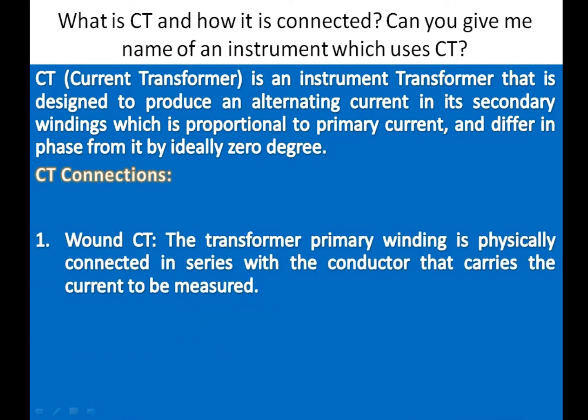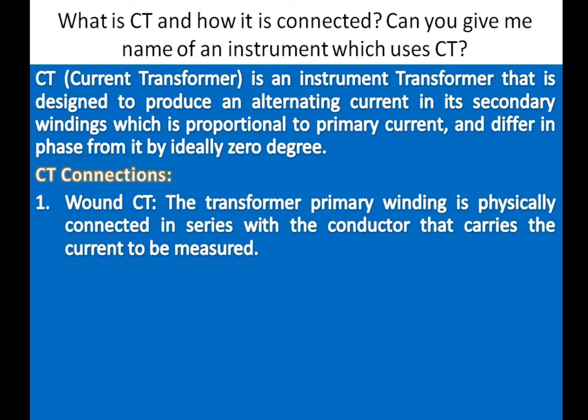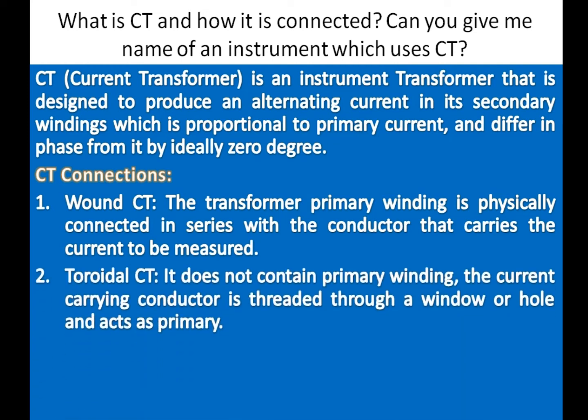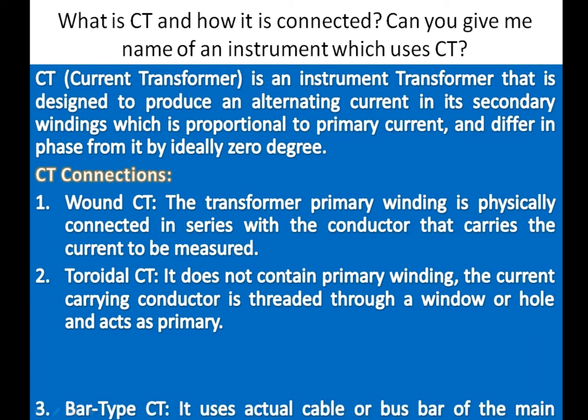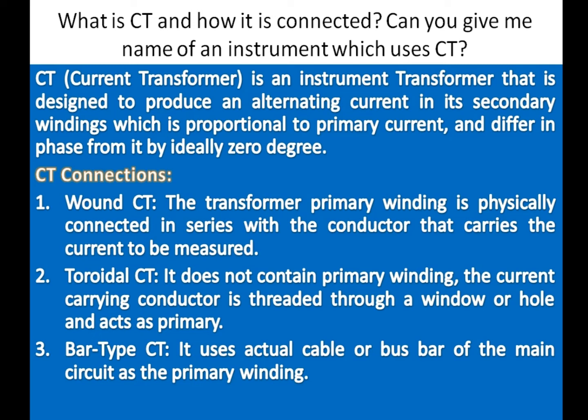CT connections. 1. Wound CT: The transformer primary winding is physically connected in series with the conductor that carries the current to be measured. 2. Toroidal CT: It does not contain a primary winding; the current carrying conductor is threaded through a window or hole and acts as primary. 3. Bar type CT: It uses the actual cable or bus bar of the main circuit as the primary winding.